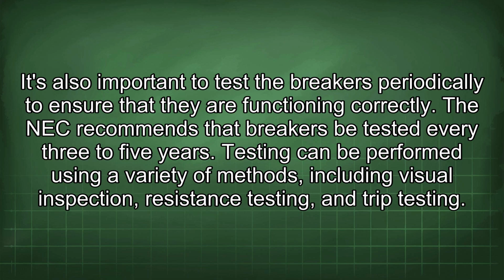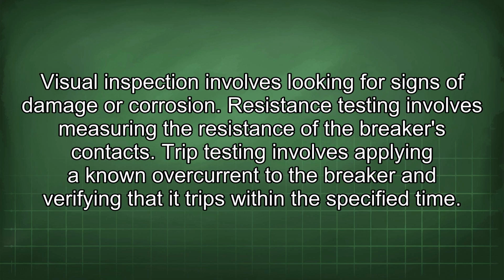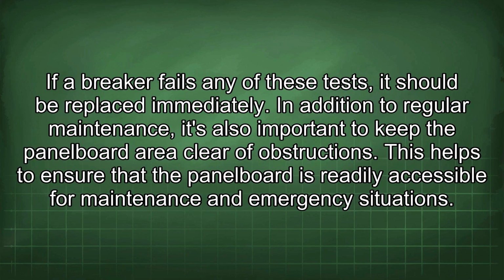The NEC recommends that breakers be tested every 3 to 5 years. Testing can be performed using a variety of methods, including visual inspection, resistance testing, and trip testing. Visual inspection involves looking for signs of damage or corrosion. Resistance testing involves measuring the resistance of the breaker's contacts. Trip testing involves applying a known overcurrent to the breaker and verifying that it trips within the specified time. If a breaker fails any of these tests, it should be replaced immediately.